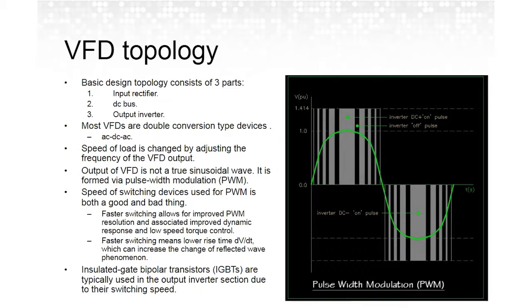Now, because we're resynthesizing an AC waveform, for all AC induction motors, the speed of the motor is directly dependent on the frequency of the power that you provide to it. So, for example, we have AC motor synchronous speeds, 3,600 RPM, 1,800 RPM, and all those are based on a base level frequency for North America of 60 hertz. So if we change the frequency, we can also change the speed of the motor. And again, based on what Ken was saying, if we change the speed of the motor, we can dramatically change the amount of power that that motor needs.